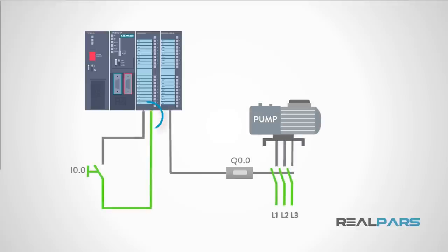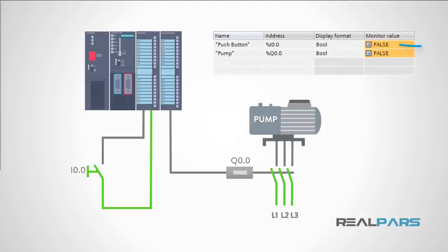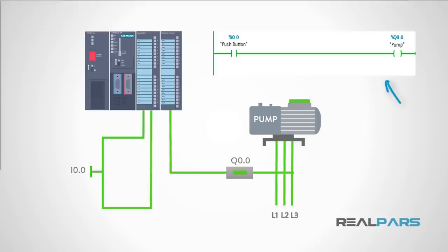If we want to monitor the state of the push button in the PLC, we would need to connect the two wires of the push button to a digital input card in the PLC. When the push button is not pressed, the PLC would see the input state as off, or as a zero. The circuit to or from the PLC input is open or not energized. When the button is pressed, the PLC input senses the change in push button state and transmits this data through a communication channel to the processor memory or data table. When the push button is pressed, the circuit to and from the PLC input is closed or energized. We could then write a PLC program, which resides in the memory of the PLC, to take some action, like turning on a lamp or a pump, when the push button is pressed.